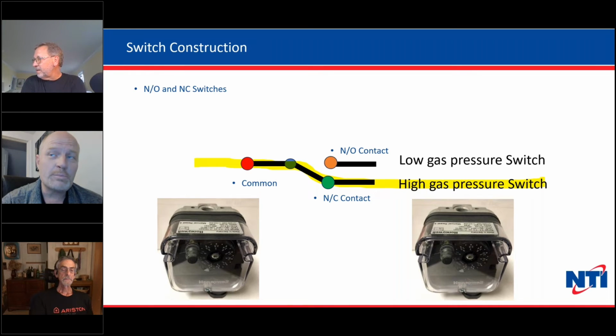The low gas pressure switch, you're probably going to have to reset this, and it's probably going to trip every single time you do a startup. That's because it goes on the gas line that feeds the boiler. And if we don't supply enough gas to feed the boiler, it trips out.